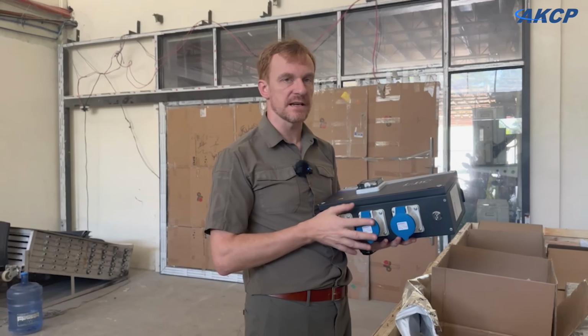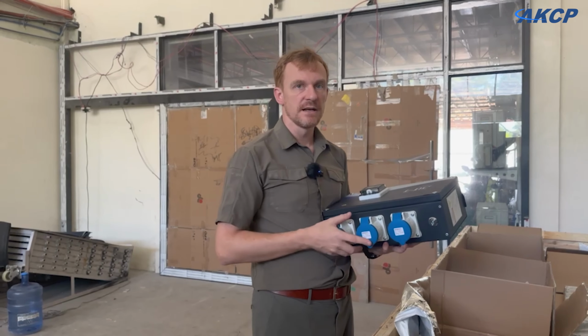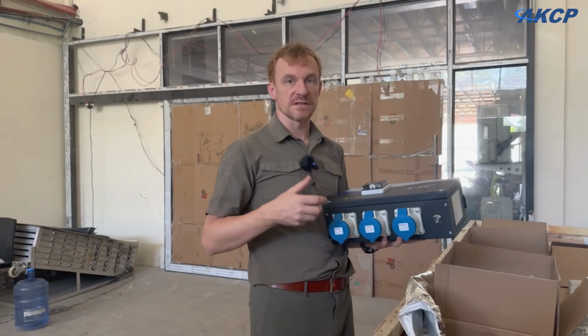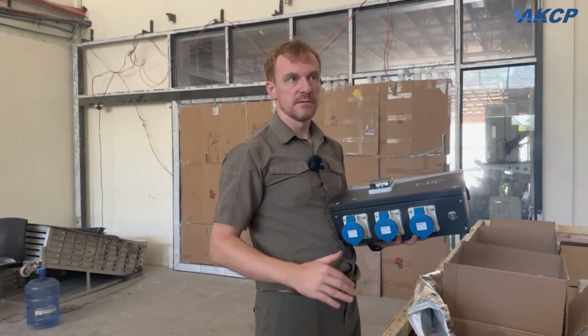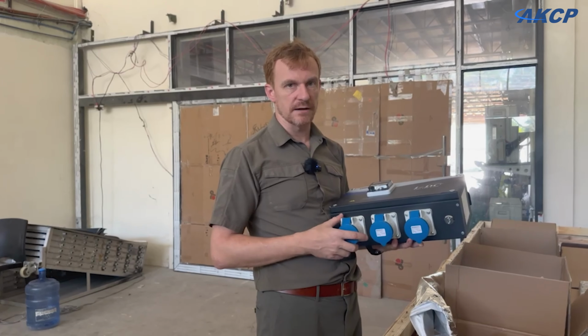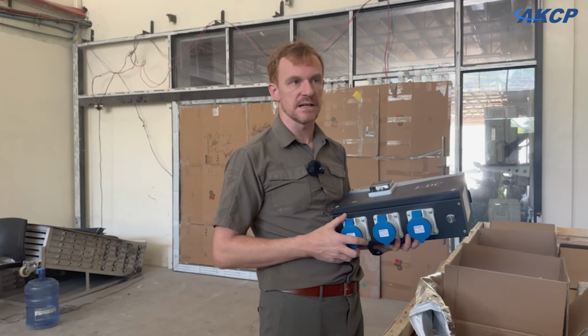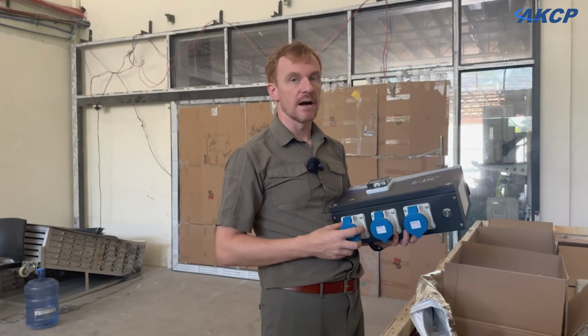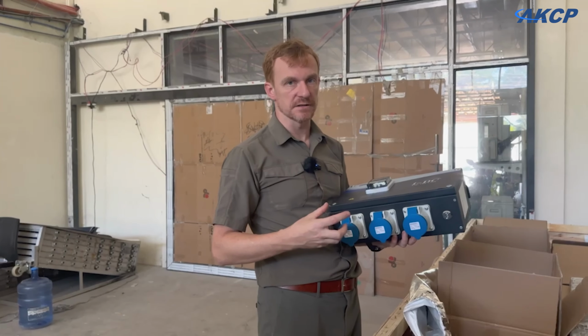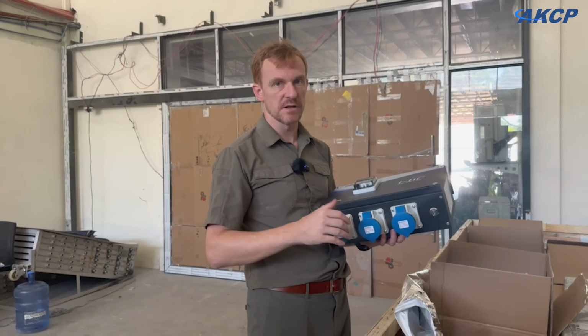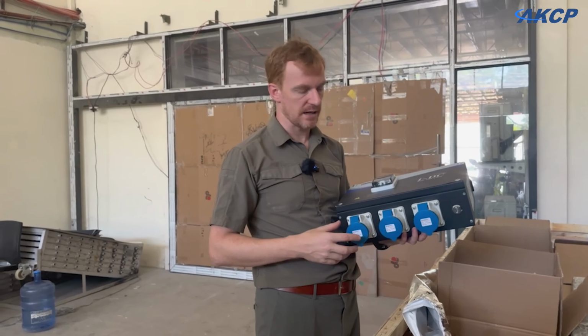In the test data center, to generate heat and simulate the servers without buying many servers that won't really be doing anything, and to generate more heat in a smaller space, we're using 9 kilowatt space heaters. They're 3 phase, and we've got 3 of those, giving us 27 kilowatts per rack.